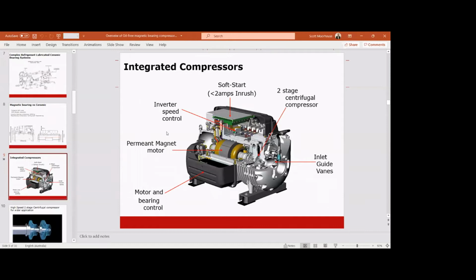One type of technology, what we call on the market, is an integrated compressor technology, where all of the components for the compressor and the speed control and the starting are assembled on the compressor. So this compressor is a two-stage centrifugal compressor, where suction goes through the first stage, through the volutes, into the second stage, and then out the discharge. We have an inlet guide vane. So for the majority of the loading and unloading, we use speed control. When we cannot unload the machine anymore, we will use the inlet guide vane or mechanical control to unload the compressor. But the majority is done by speed, because this is the most efficient way to unload a centrifugal compressor.